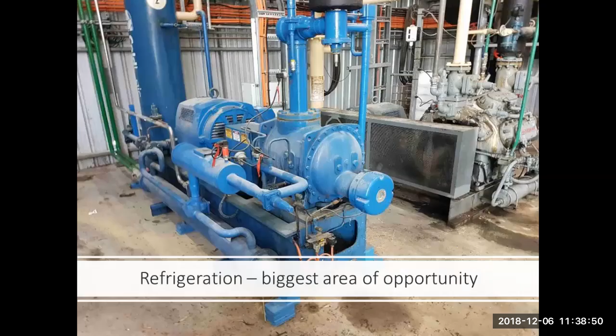But one of the main things to ask is what actually makes wineries different. Wineries are subject to high variations in seasonal use. So your energy use can vary dramatically throughout the year. During vintage, you use heaps of electricity, but throughout the rest of the year it can be quite low. Alongside this, you've got high electricity costs as well. One of the things that makes wineries really interesting is that you've got a lot of thermal storage available in the wine. That allows wineries to be one of the industries that can actually manage demand by changing practices in the winery and changing how you operate.